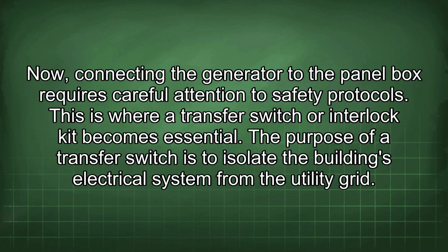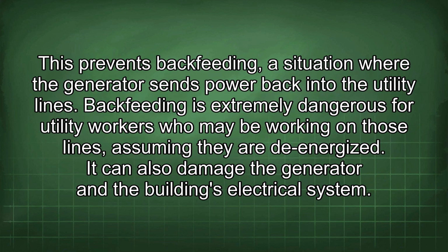Now, connecting the generator to the panel box requires careful attention to safety protocols. This is where a transfer switch or interlock kit becomes essential. The purpose of a transfer switch is to isolate the building's electrical system from the utility grid. This prevents backfeeding, a situation where the generator sends power back into the utility lines. Backfeeding is extremely dangerous for utility workers who may be working on those lines, assuming they are de-energized. It can also damage the generator and the building's electrical system.